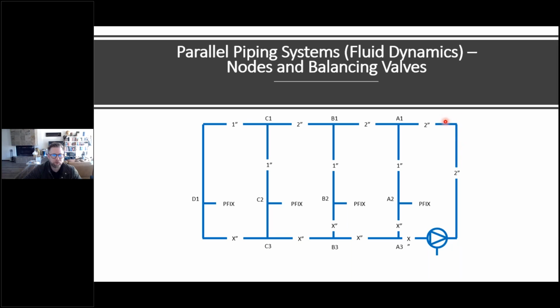So leaving the mechanical room, coming out, and let's assume it's to scale just for ease of concept, we get to a nodal point A1. The flow at that point, assuming a closed system for hot water return systems, which is typically our initial assumption, diverges and you have it continuing on to the B and C loops and D loops, and then some of the piping going through A. And we're trying to figure out what the size is of our return lines. So the return line starts downstream of every plumbing fixture.